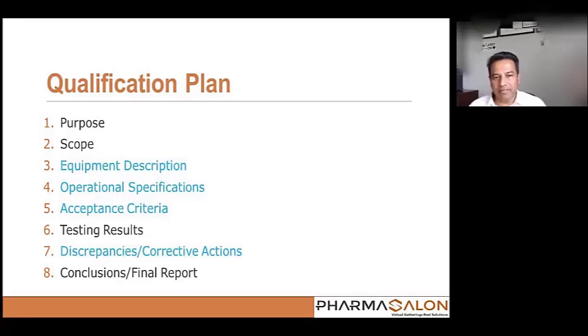There is an equipment validation document, which can be done in-house by quality assurance, or they can have a third party do the validation. Anytime prior to making any batches and releasing, the equipment must be qualified. When the qualification is done by a third party, they also use certain instruments, which must also be certified. They need to have a NIST certification or any other certification, such as for thermocouples, temperature probes or thermostats, any of those used in the qualification processes.